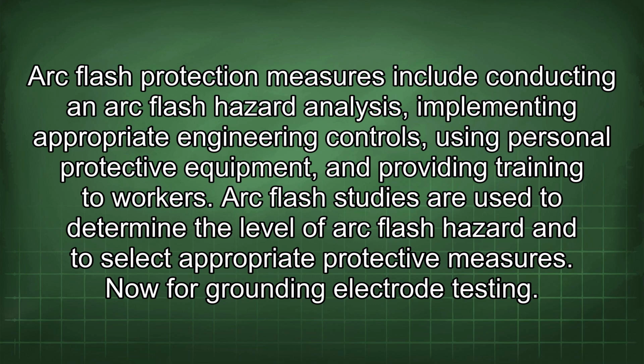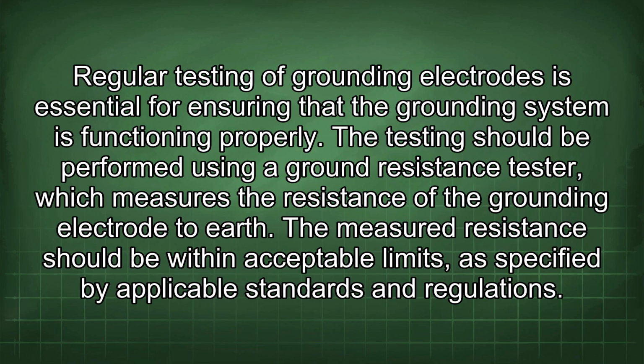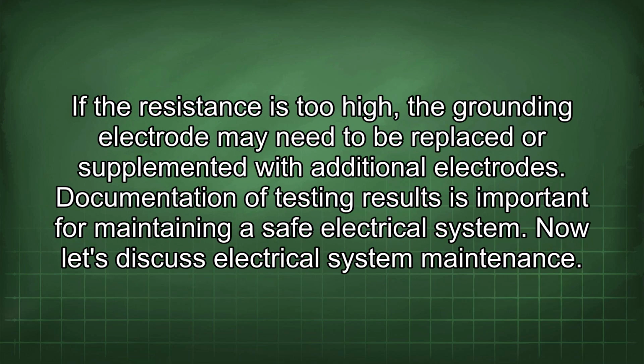Now for grounding electrode testing. Regular testing of grounding electrodes is essential for ensuring that the grounding system is functioning properly. The testing should be performed using a ground resistance tester, which measures the resistance of the grounding electrode to earth. The measured resistance should be within acceptable limits, as specified by applicable standards and regulations. If the resistance is too high, the grounding electrode may need to be replaced or supplemented with additional electrodes. Documentation of testing results is important for maintaining a safe electrical system.